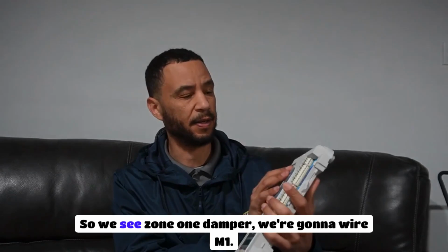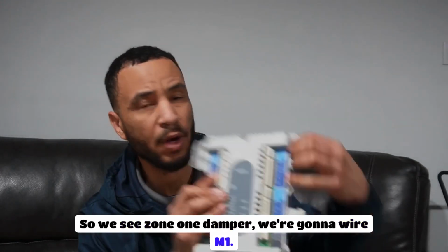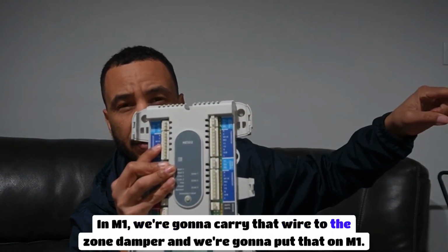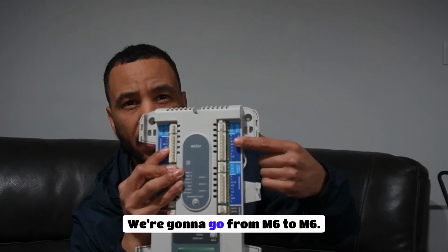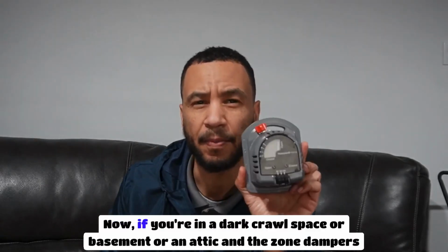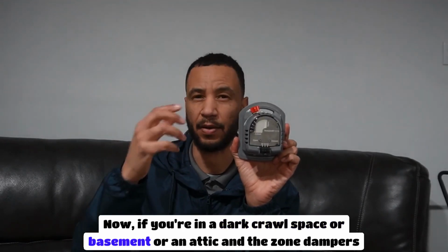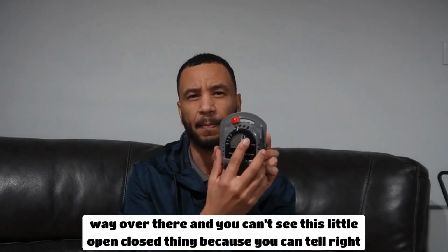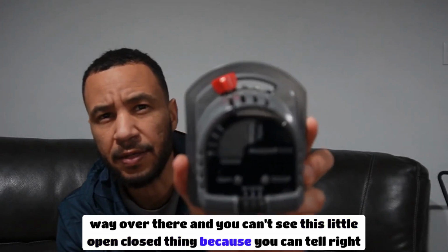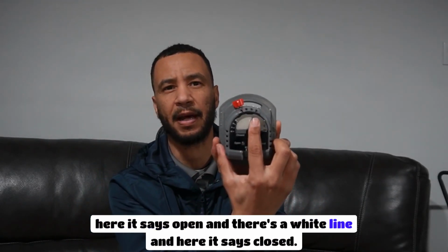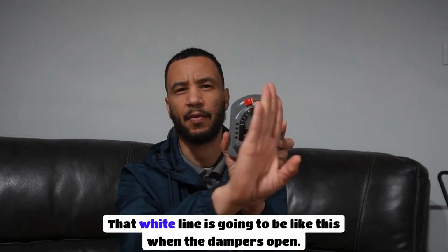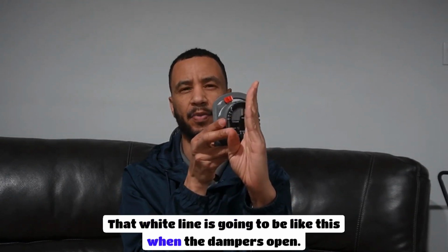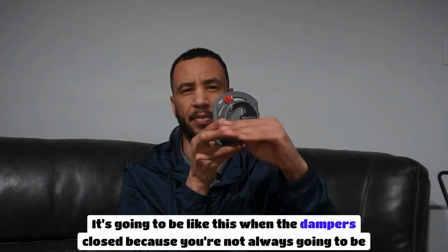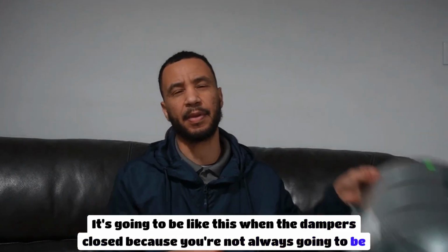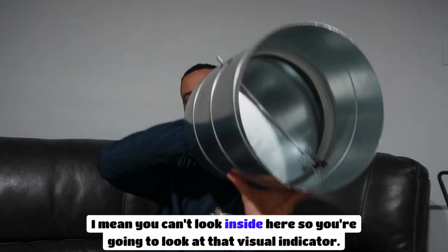So we see zone 1 damper, we're going to wire M1 in M1. We're going to carry that wire to the zone damper and we're going to put that on M1. We're going to go from M to M. Now, if you're in a dark crawl space or a basement or an attic and the zone damper is way over there and you can't see this little open close thing, you can tell right here it says open and there's a white line and here it says closed. That white line is going to be like this when the damper is open and it's going to be like this when the damper is closed, because you're not always going to be able to look. I mean, you can't look inside here. So you're going to look at that visual indicator.